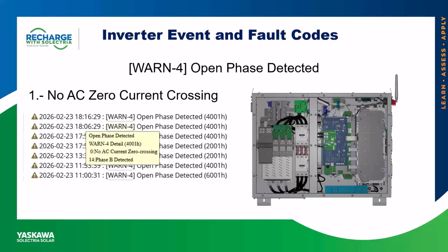As you can see in the picture, when you hover over the fault code, it says bit 0, no AC current, 0 crossing. And then it says bit 14, phase B detected. This code can also be tied typically with a crit 13. And 90% of the time, what it's going to be pointing to is a problem with one of your CTs, the current sensing devices that are after the IGBTs, as we saw earlier in the presentation.